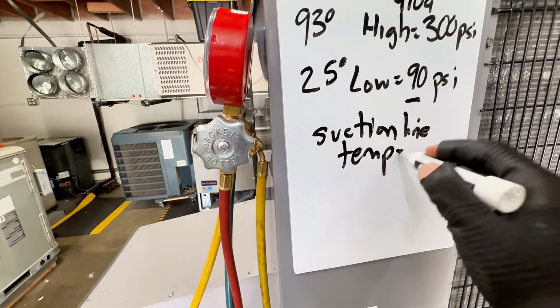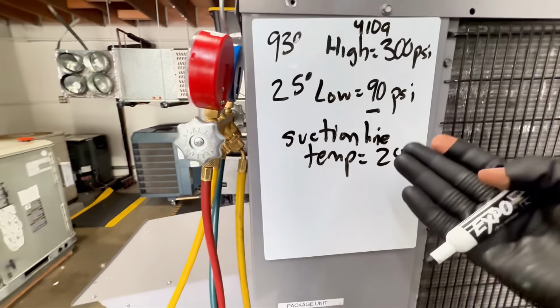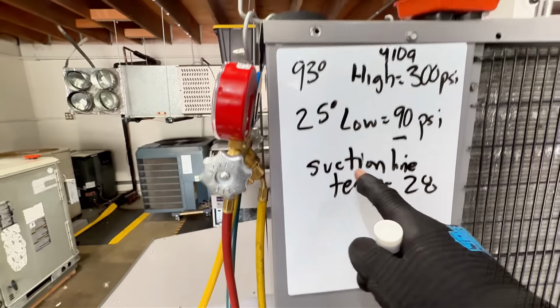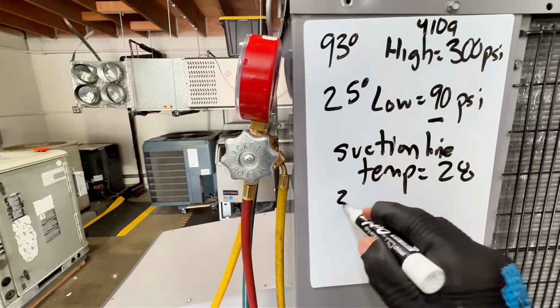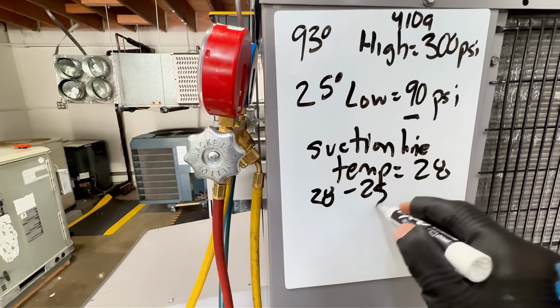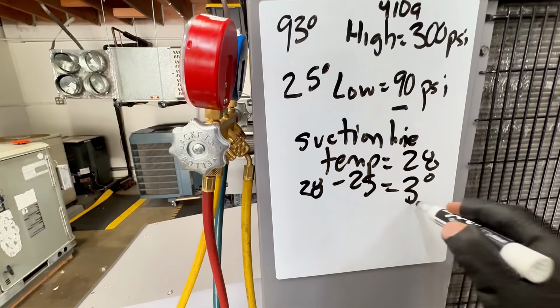So my suction line temp is 28 degrees. Remember superheat? Suction line temperature minus evaporator temperature. So 28 minus 25, I have 3 degrees of superheat. Okay, so then my subcool.